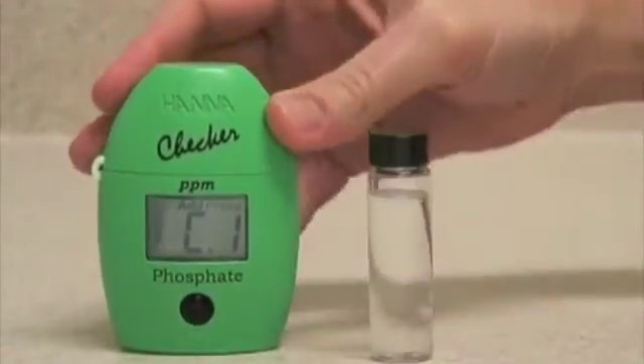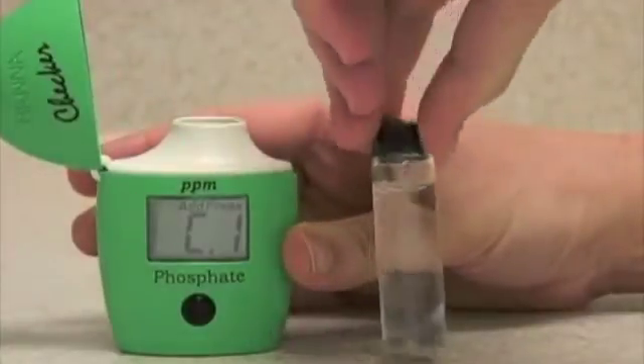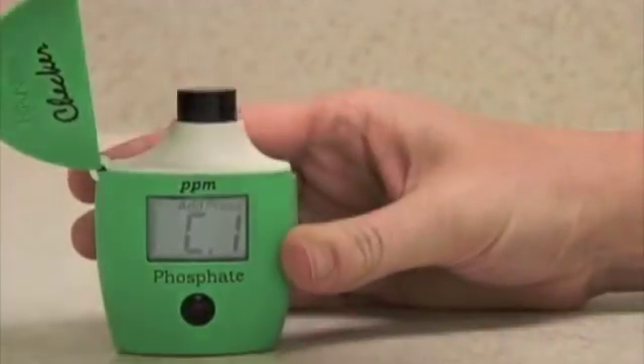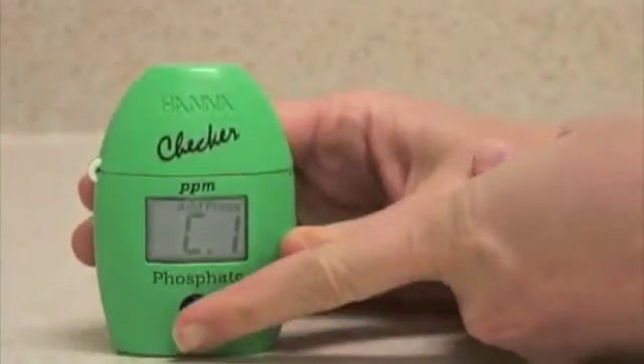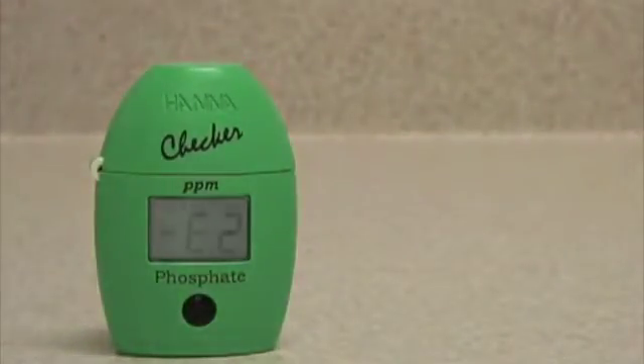When it displays C1, you use a blank sample to zero the instrument. Insert the vial into the meter and press the button again. It will flash bars at you to let you know it's sampling.